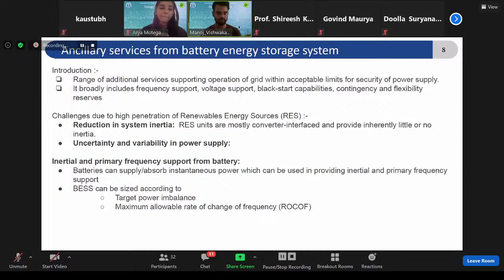So our focus is on supplying inertial and primary frequency support, specifically from the battery. We can also supply these services from PV and wind, but our focus is on how the battery can provide them. The battery will also be supplying energy in the deficit periods, and here we are using it also for inertial and primary frequency support. Given the battery's nature of instantaneous power supply, we are using batteries, and these can be sized for this application according to the power imbalance in the grid and the maximum rate of change of frequency during any frequency deviation.